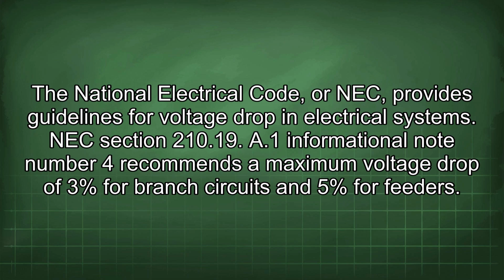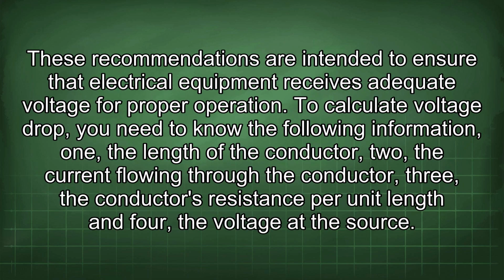The National Electrical Code, or NEC, provides guidelines for voltage drop in electrical systems. NEC Section 210.19(A)(1) Informational Note Number 4 recommends a maximum voltage drop of 3% for branch circuits and 5% for feeders. These recommendations are intended to ensure that electrical equipment receives adequate voltage for proper operation.